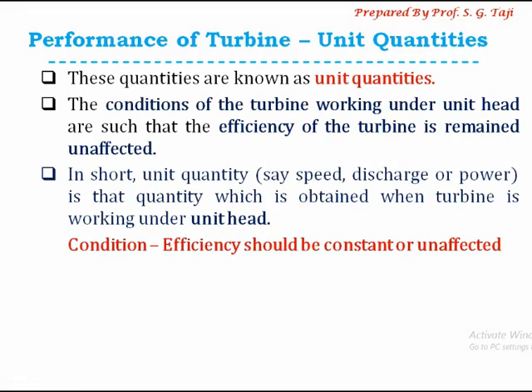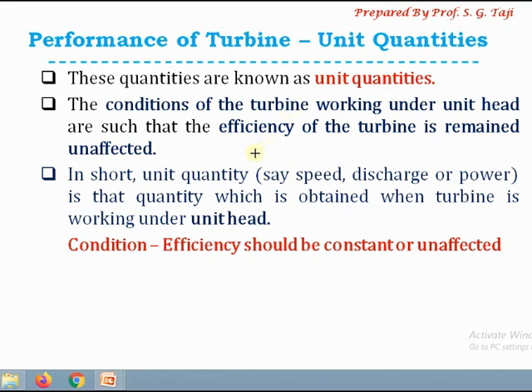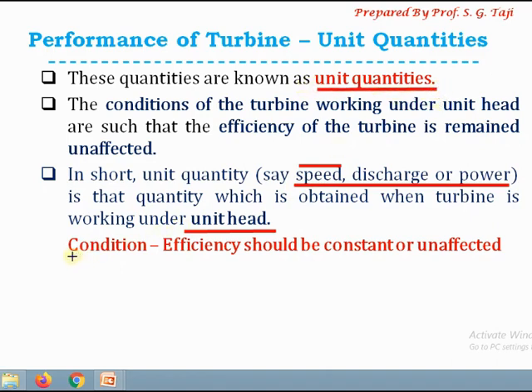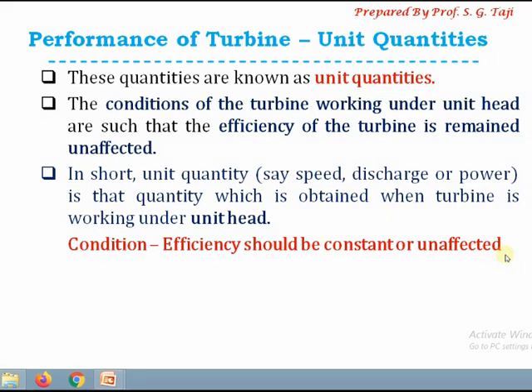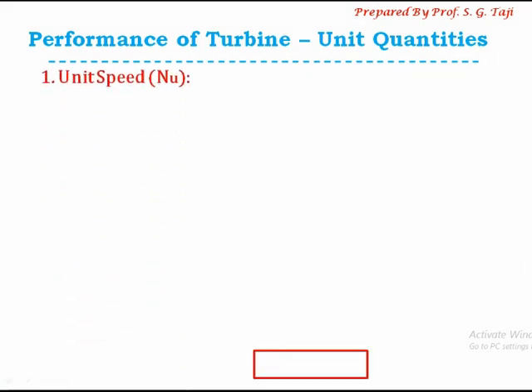So let's go to the definition of unit quantities. In short, unit quantity is that quantity which is obtained when the turbine is working under unit head. Whenever we reduce the head on the turbine to unity, the value of that quantity is known as unit quantity. Generally we consider three unit quantities: unit speed, unit discharge, and unit power. The condition is that efficiency is maintained as constant and unaffected.